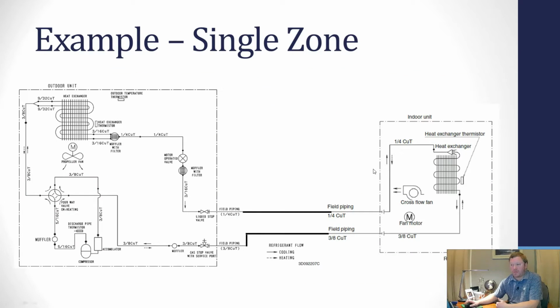And if you like actual schematics, I went and grabbed one. This one is from Daikin's website, where it shows you the compressors at the bottom left, and in the heat mode, that refrigerant is going to come off the compressor, go through that 4-way valve. It's going to go to the indoor unit. It's going to go through the indoor unit heat exchanger, reject all of that heat energy into the space, condense into a liquid. It's going to go back to the outdoor unit. There's your expansion valve. That's where you're going to get that pressure drop. Then again, that liquid, remember that liquid needs to be colder than the outdoor air so that it can absorb that heat energy and evaporate through the outdoor heat exchanger before it then comes back to the compressor. So depending on which picture is easier to understand, I thought it was important I give you an actual schematic and not just my drawn up one.